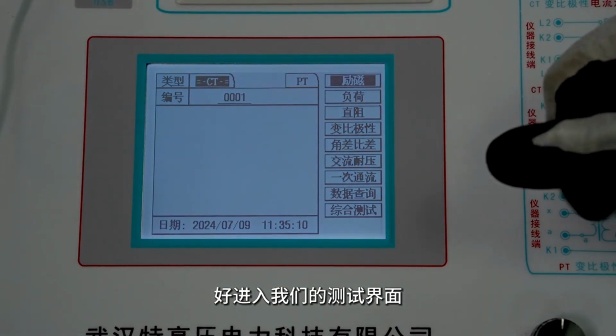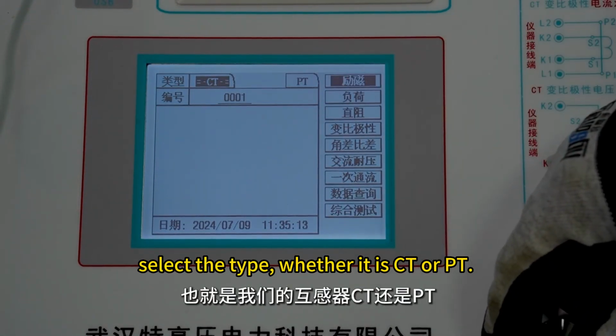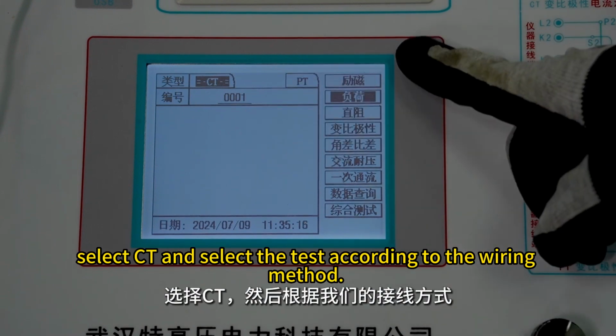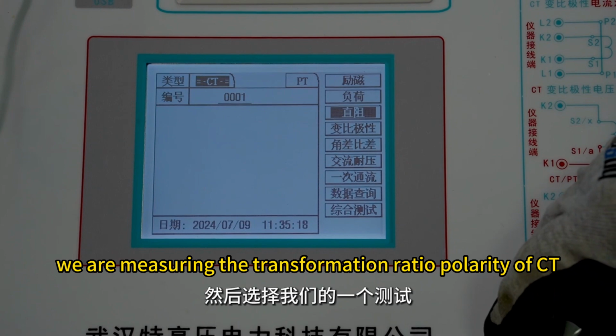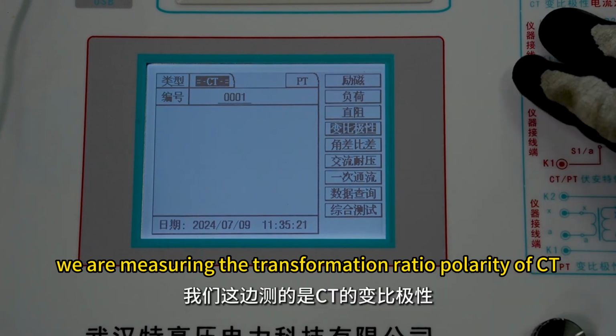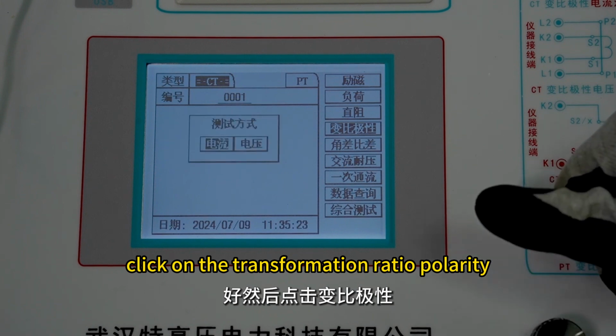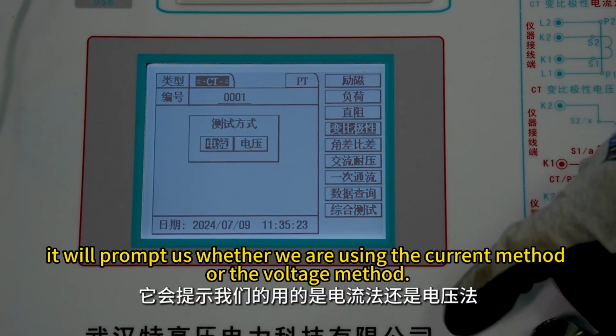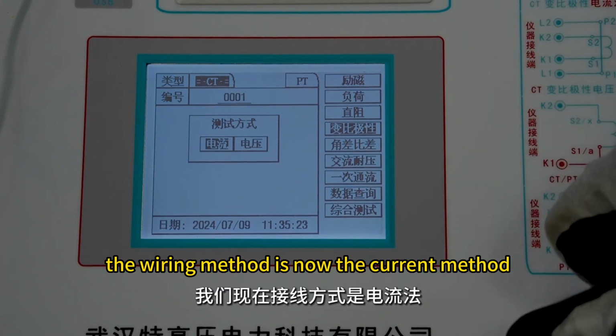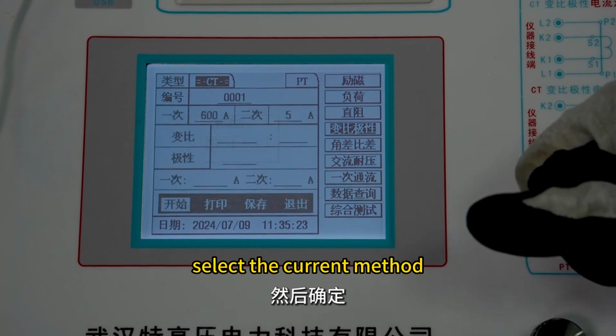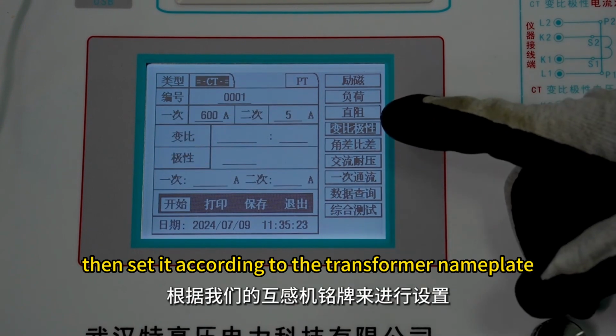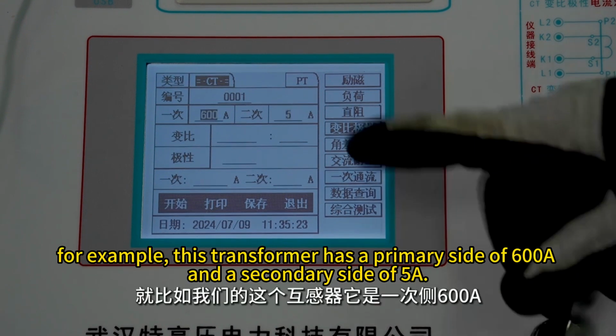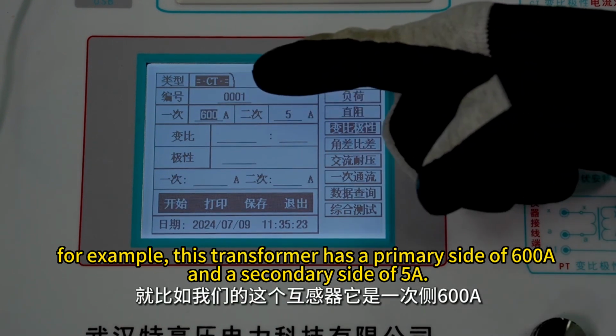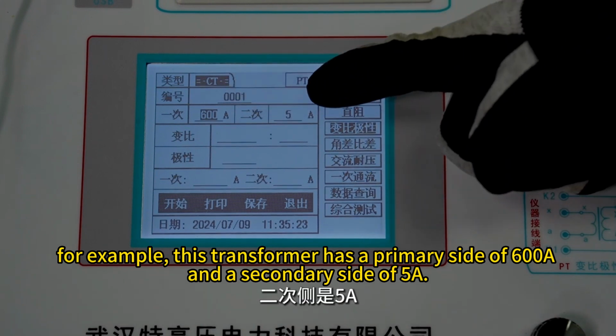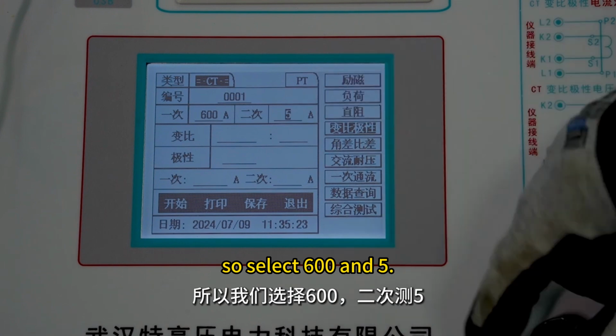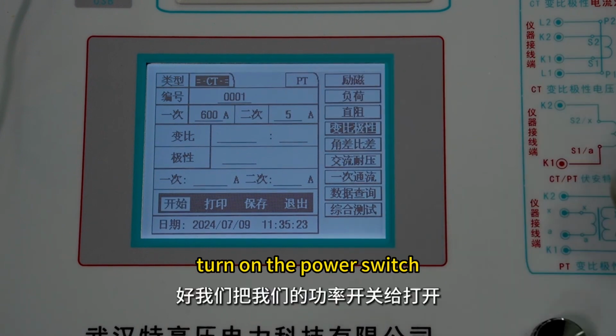Enter the test interface. Select the type, whether it is CT or PT. Select CT and select the test according to the wiring method. We are measuring the transformation ratio polarity of CT. Click on the transformation ratio polarity. It will prompt us whether we are using the current method or the voltage method. The wiring method is now the current method. Select the current method. OK. Then set it according to the transformer nameplate. For example, this transformer has a primary side of 600 ampere and a secondary side of 5 ampere. So select 600:5. After setting, turn on the power switch.